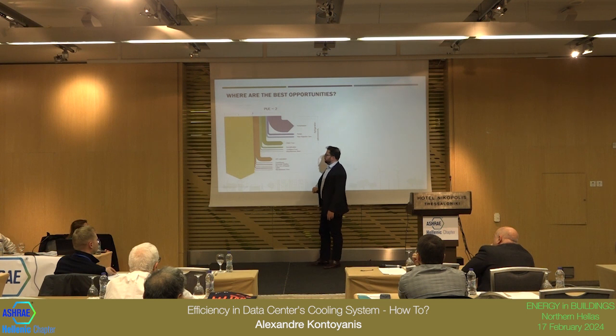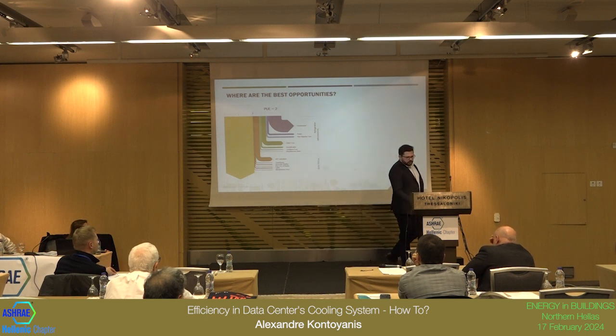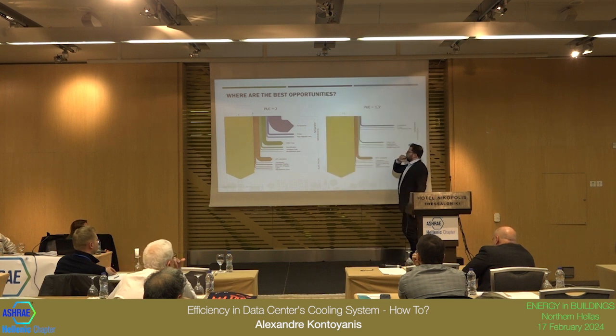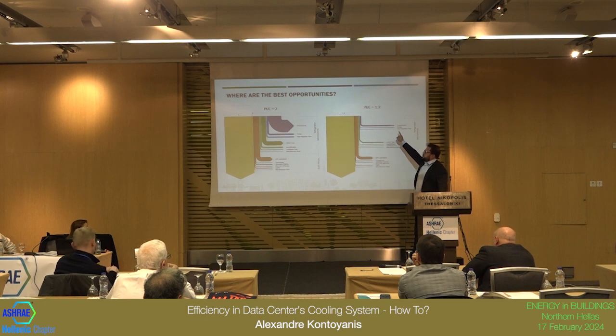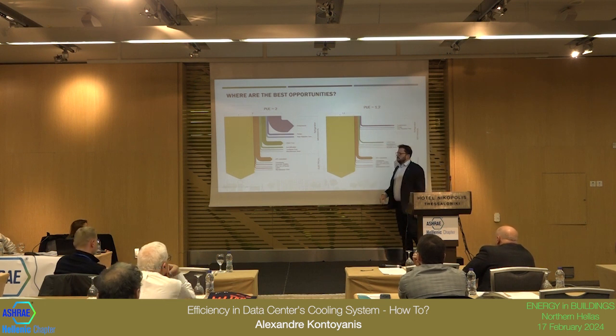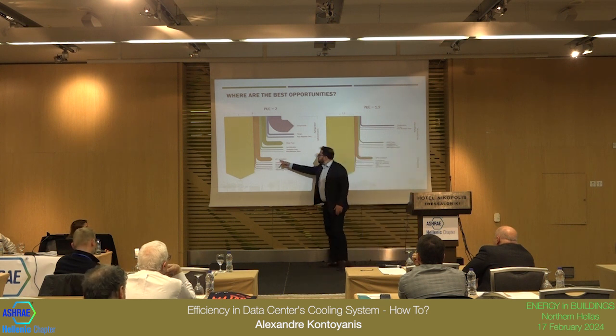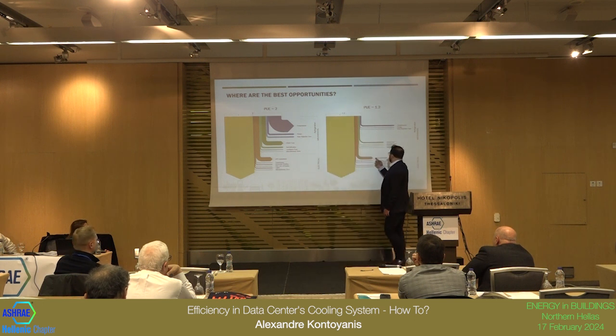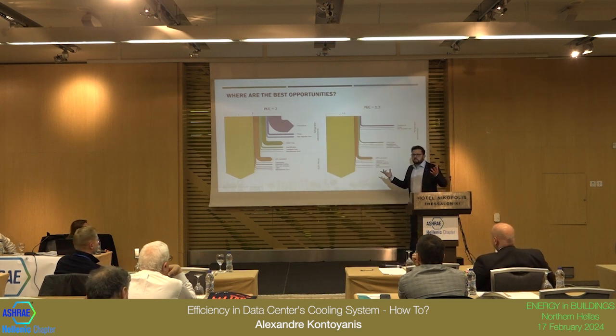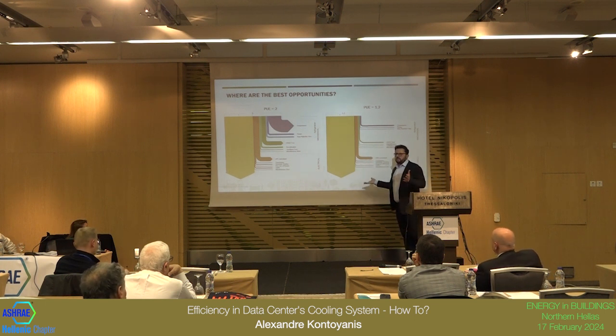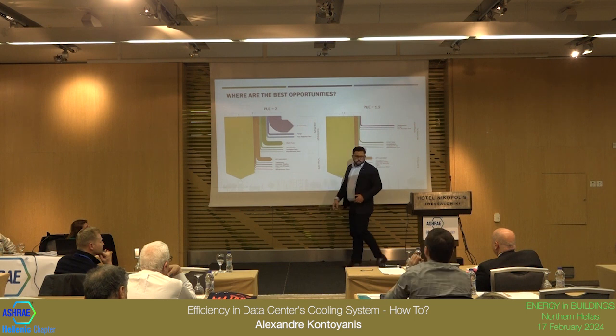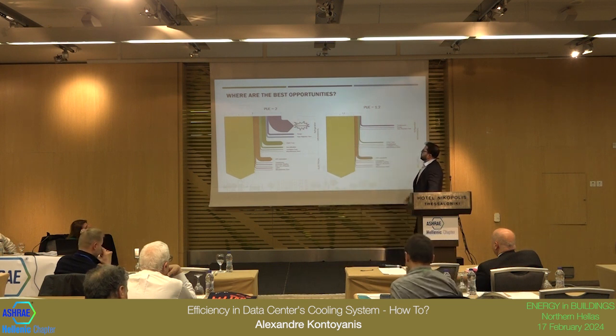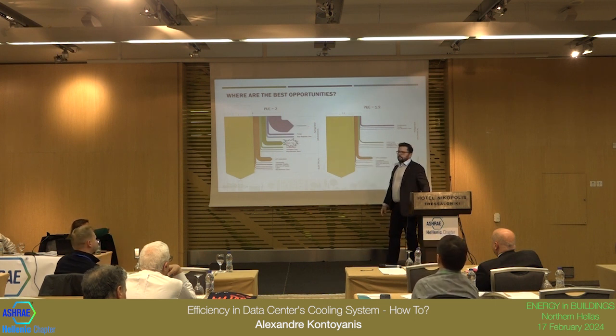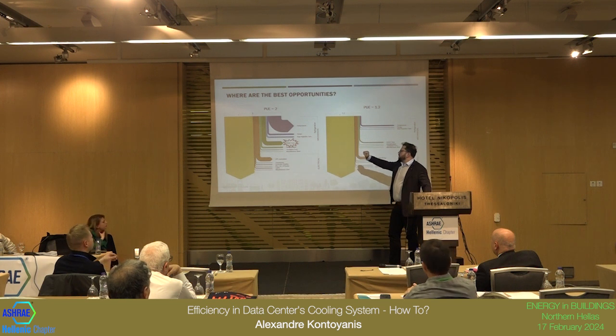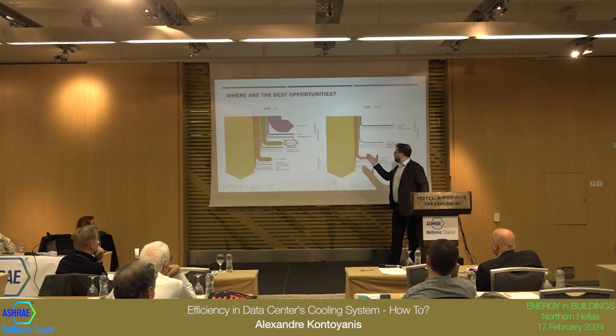UPS, of course, consumes a lot. But when you look at a typical efficient data center, look at the difference in the consumption of the compressors or the fans. Now look at the difference between an average UPS and a state-of-the-art UPS. It's 5% of 5%, and you need to invest a lot of money to change your UPS. So we can say that the best opportunities are in the compressors and the fans. You have, of course, humidification, etc., but in 20 minutes, let's talk about those two, the more important ones.